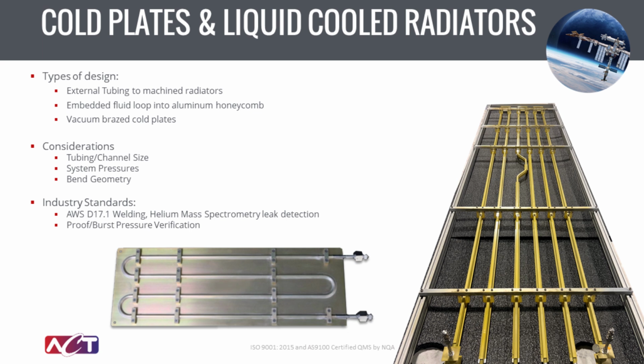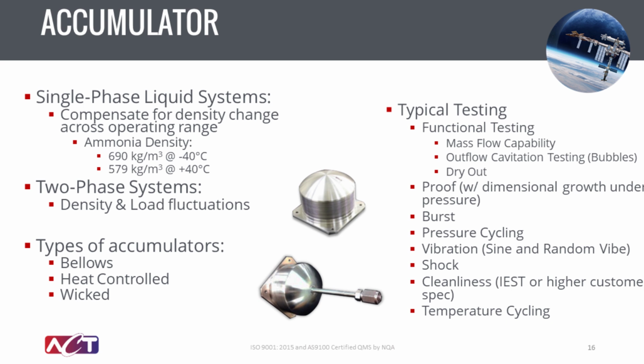And in terms of some of the industry standards that are very routinely flowed down on these types of systems, welding, similar to heat pipe technology, goes through the same welding standard. AWS D17.1 is a fairly standard welding process to adhere to, to make sure we have very robust joints and limit failures. And then most of these systems are helium mass spectrometry leak detected, as well as go through fairly rigorous proof and burst pressure testing. So at the end of the day, we want to make sure nothing being flown fails for something that's fairly minor. So they do go through fairly intense testing protocols.